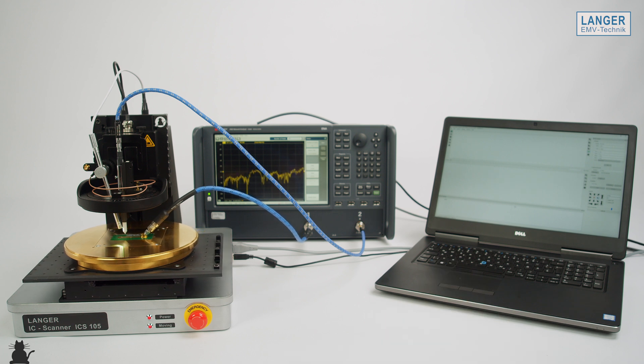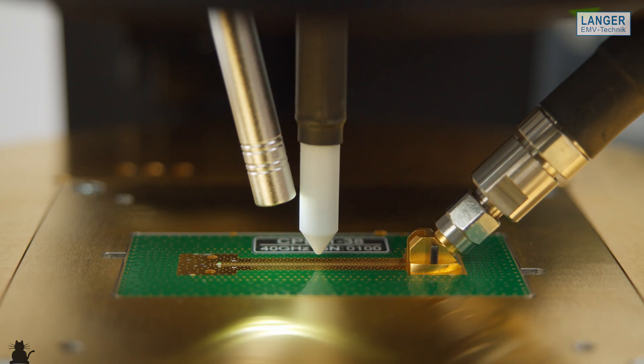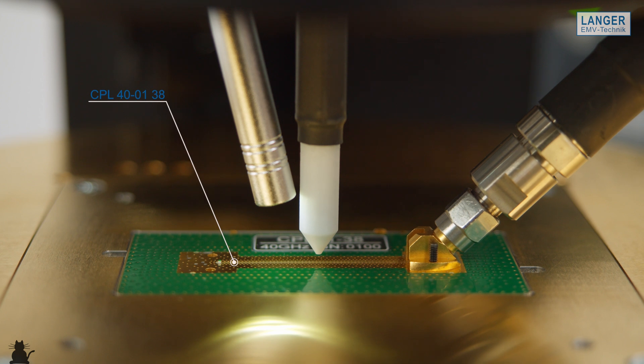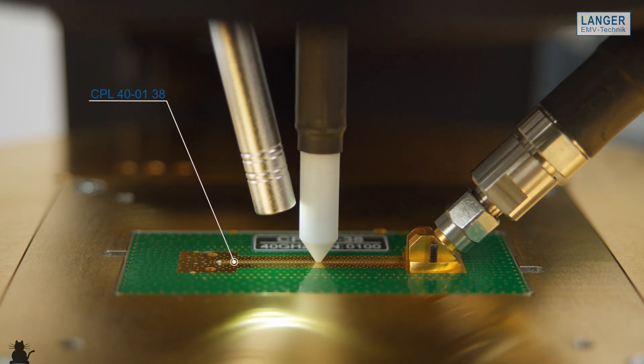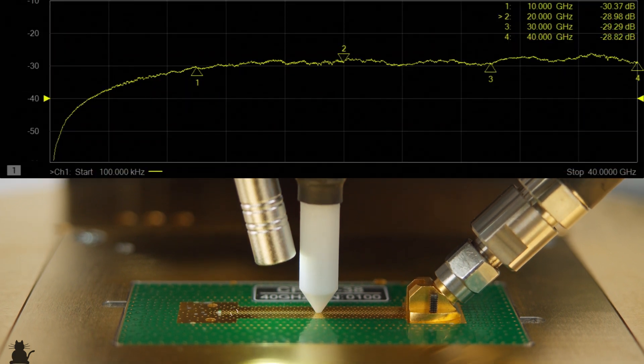The Langer stripline CPL400138 is suitable for calibrating the HRE41. The transmission behavior of the near-field probe is almost constant in the frequency range from 8 to 40 GHz and thus enables reproducible measurement results, for example to verify and refine simulation models.